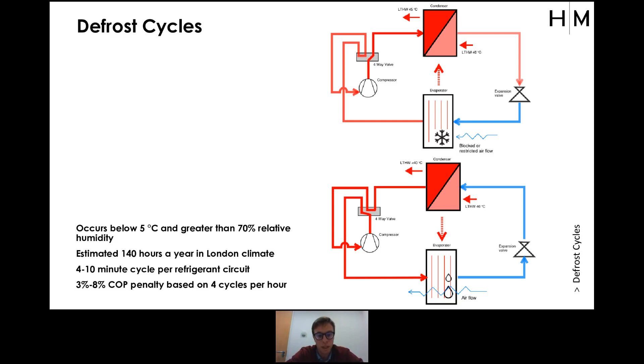selections or design considerations is looking at multiple circuit air source heat pumps. If you've got a single circuit, you'll have to find a reservoir of heat when you go into this defrost cycle, so that it will take energy from your network. Or if you go for a multi-circuit system, they can actually regenerate each other. So one circuit will go into a defrost cycle, the other one just purely provides energy at full operation to the defrosting circuit. That would obviously mean that you're not generating energy for the network, so you have to meet your demand by other means, and that's where you need to consider thermal storage or other supplementary systems or other modules of air source heat pump.